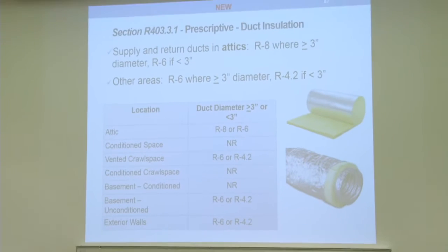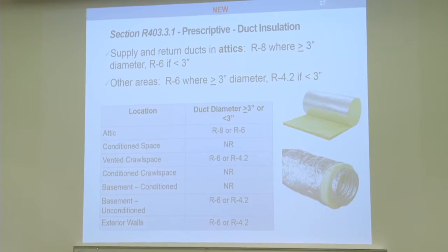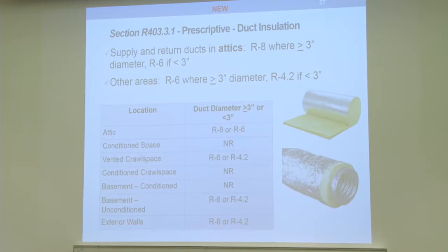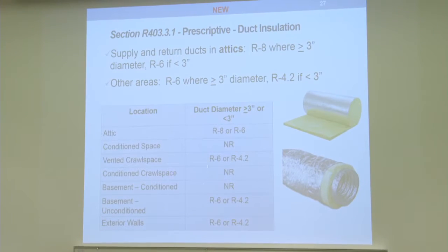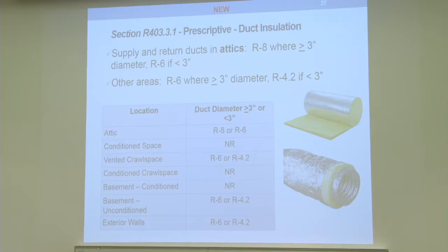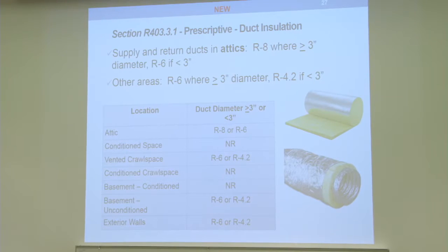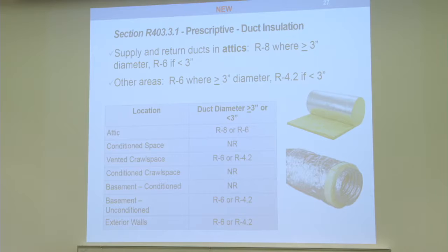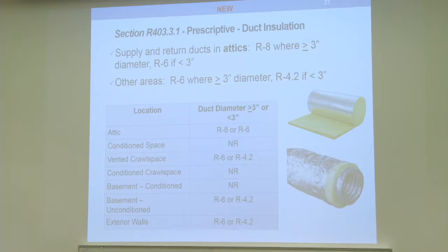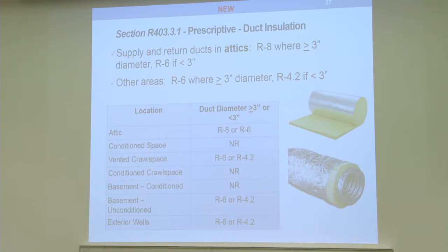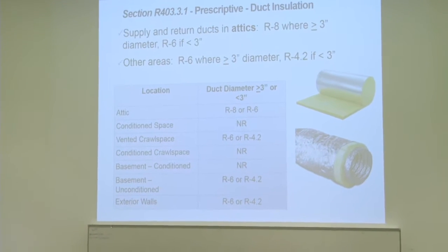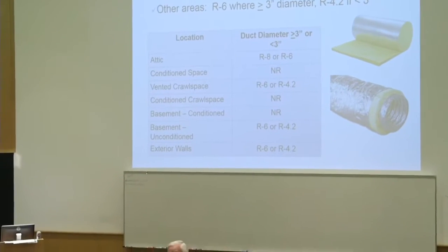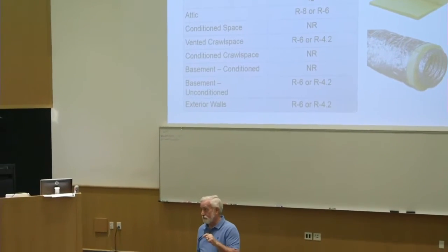We have a change, and you expect changes coming forward on duct insulation. The only change is that if you have a duct that is smaller than 3 inch, like you would have in a high velocity system, the insulation only has to be R4.2. That being said, everything else is the same, R6 in a crawl space, R8 in an attic. There is a huge movement towards burying ducts in insulation in attics, and it's a good one.